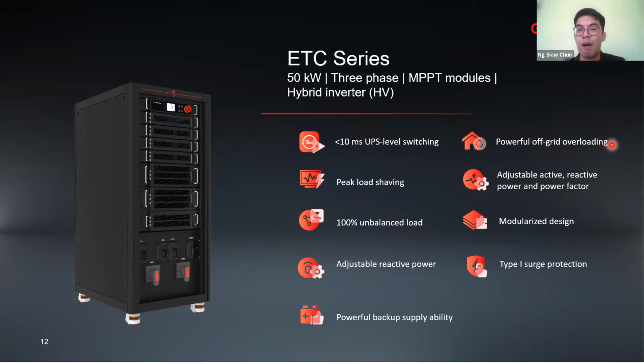What we mean by powerful is that, first of all, we support 110% overloading for a long time, 150% for more than 60 seconds, and 200% overloading for 10 seconds. So by this, we can also handle any inrush current, and it is suitable for the off-grid solutions. At the same time, we also provide optional type 1 SPD protection for our PCS here.